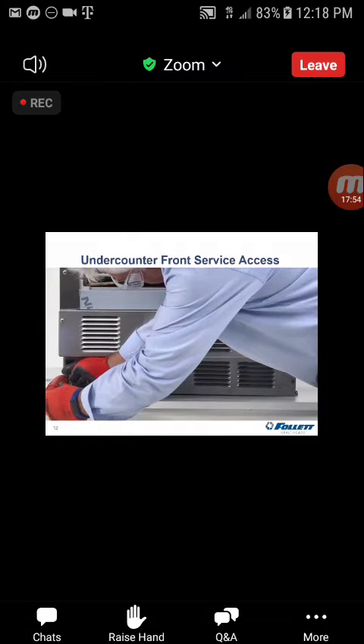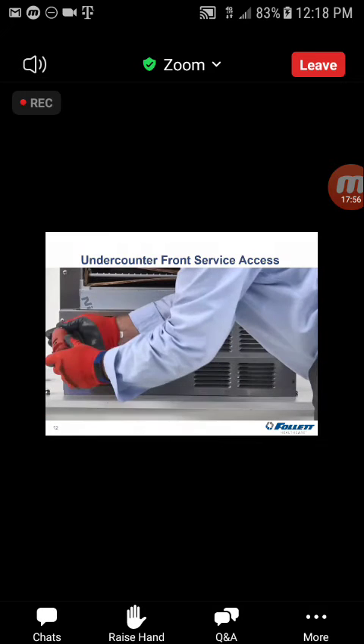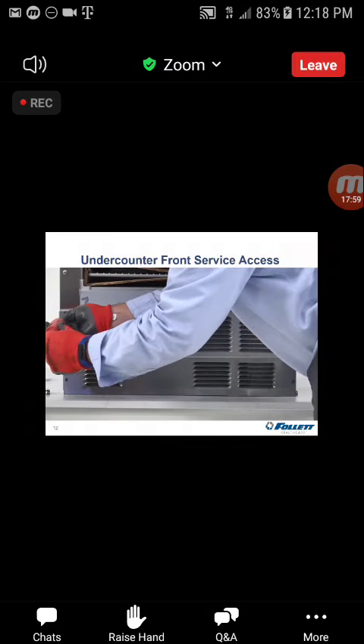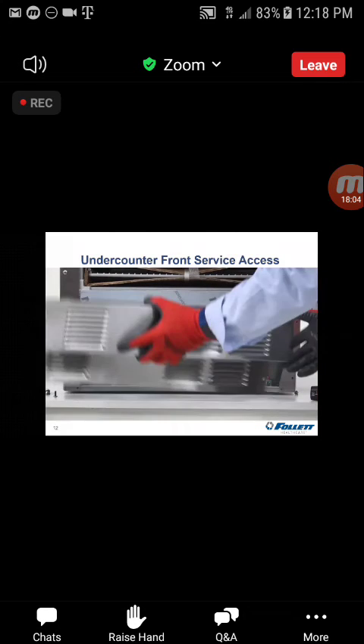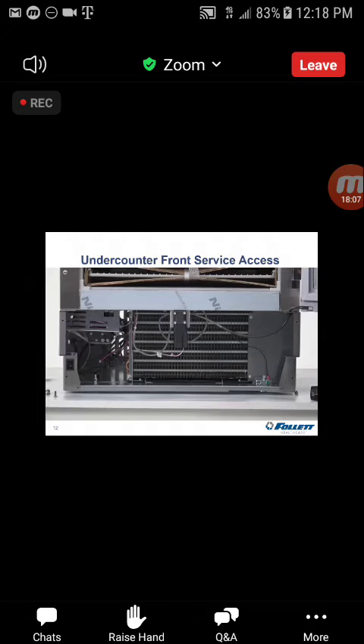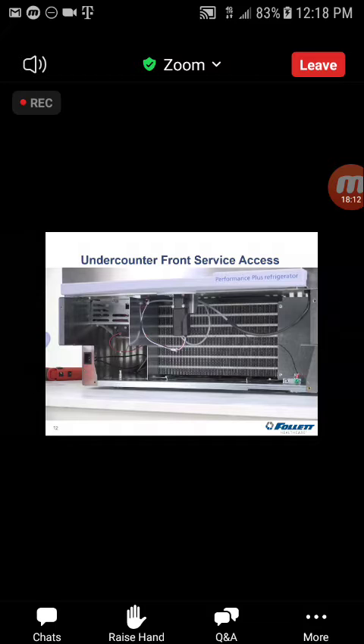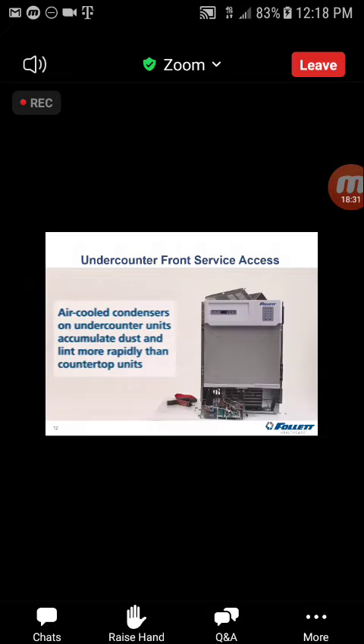Both the air-cooled condenser and the electrical control box and control board are accessed from the front of the unit. For units that have a touchscreen, there is a door alarm sensor installed in the front panel, so take care when removing the panel. As with any refrigerator or freezer, the air-cooled condenser needs to be kept clean. On the Follett under-counter refrigerators and freezers, the condenser is accessed from the front. By removing the lower front panel, the condenser can be seen on the right-hand side of the unit. All Follett under-counter units have baffling to prevent recirculation of exhaust air coming off of the condenser. The units will totally front breathe.